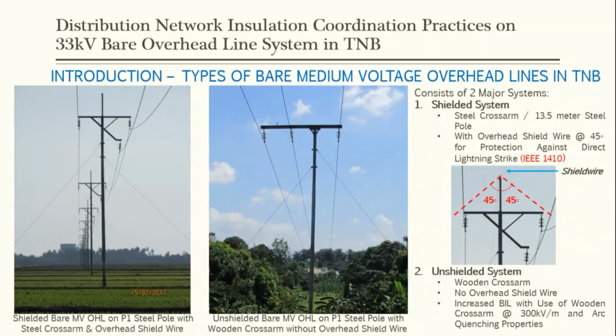For the bare medium voltage overhead lines, it can be categorized into two major systems. First, we have the shielded system. Okay, the shielded system is on the left. The shielded system has steel cross arm with 13.5 meter steel pole and with an overhead shield wire at a 45-degree angle for protection against direct lightning strike. Okay, we have the shield wire up here at a 45-degree angle.